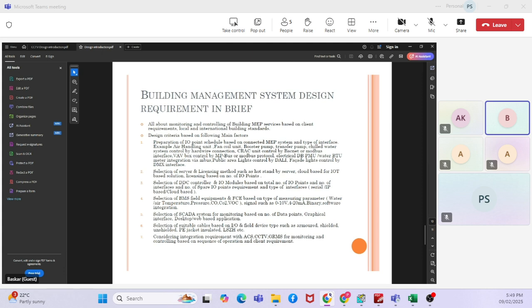When we go for AHUs, we might have the control schematic received from the client. If it's not there, we need to propose based on our understanding whether we need to monitor the temperature of the water in and water out, chilled water in and chilled water out, or whether we need to monitor the CO2 level in the duct. When we go for the car parking, maybe we need to monitor CO. So all the sensors have to be chosen based on the client requirement, the control schematic, and the IO point schedule.